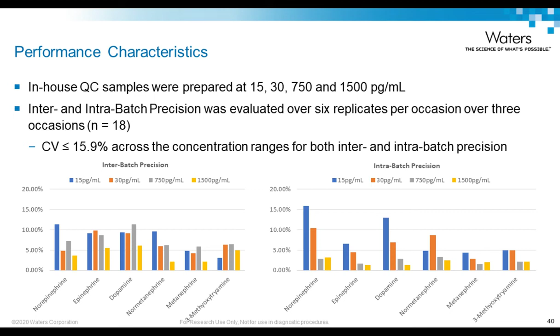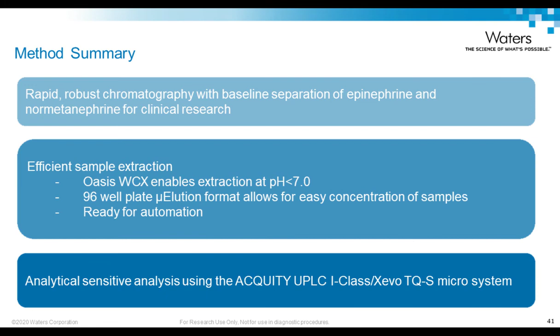So in summary, for this particular method, a reverse phase chromatographic method was employed to provide a rapid, robust separation with baseline resolution of interferences. An efficient sample preparation method using solid phase extraction provides extraction of polar analytes from plasma at lower pH in a 96 well plate microelution format, with the option to automate the method using a liquid handling system in the future. The Acquity UPLC I-Class Xevo TQS Micro system enables detection at low physiological concentrations of catecholamines and metanephrines for clinical research, providing better detection limits compared to entry-level systems.